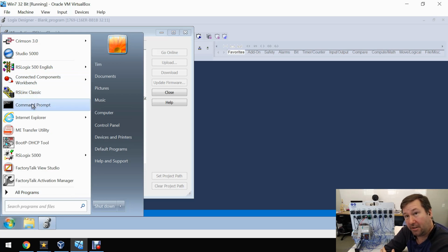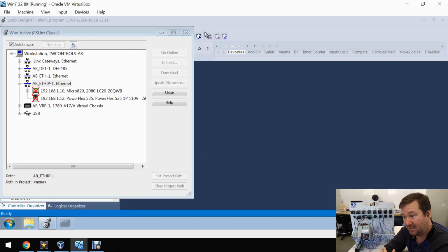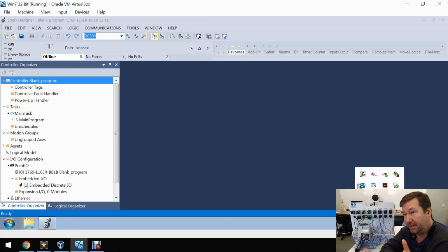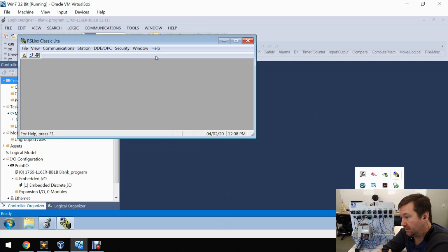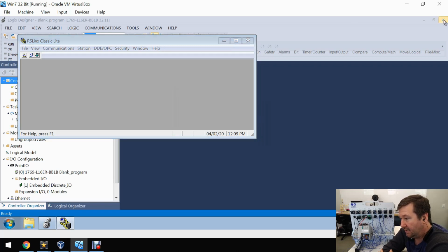So now we're going to go to command prompt. This is the only intelligent thing I do in this video until I actually solve the problem. We're actually going to ping it. And we see, all right, I can ping my PLC. So yeah, what do? I close it and I open up the regular RsLinx. Like that's going to do any good. And yeah, we get the red X's again.